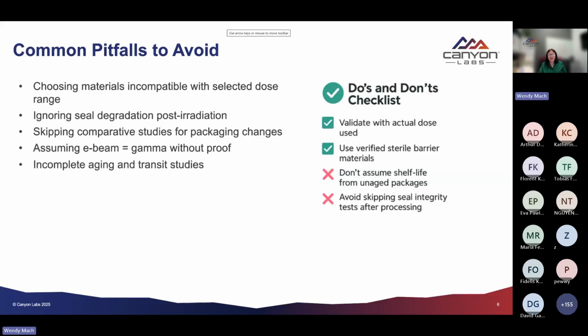Making sure that you understand that and when to schedule those as part of your validation is critical, because a lot of times this is where a lot of your timeline will get sucked up. Accelerated aging, even though it's accelerated, will continue to cover a lot of time. 1 year in a chamber is still 46 days. So making sure the packaging is brought in the very beginning is one of those critical points.